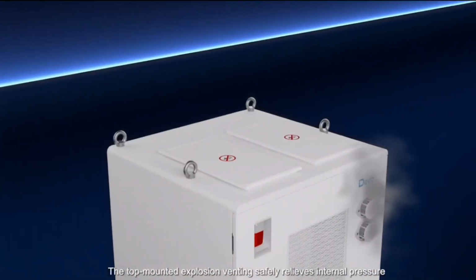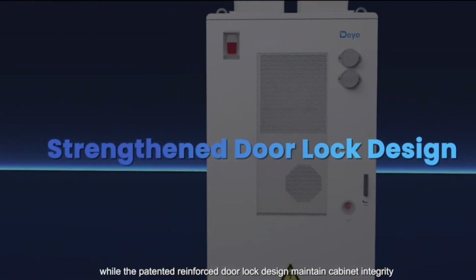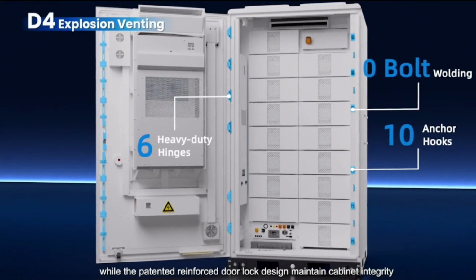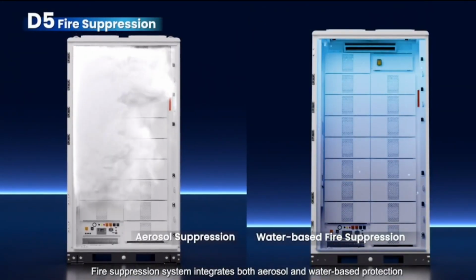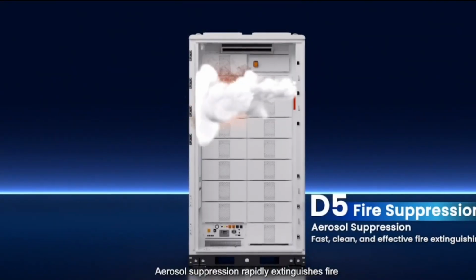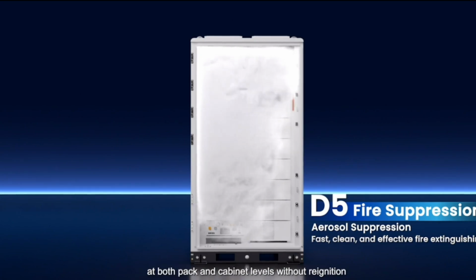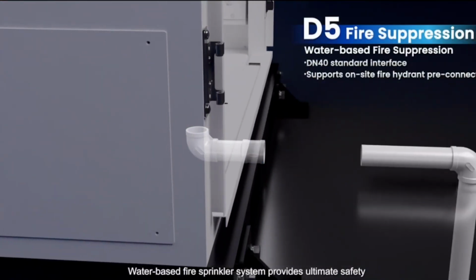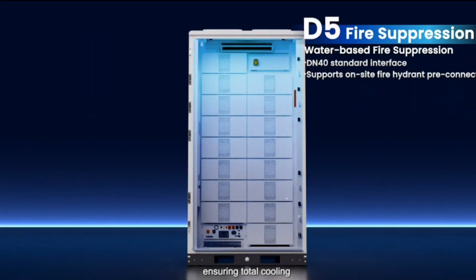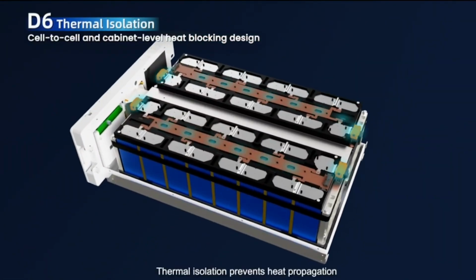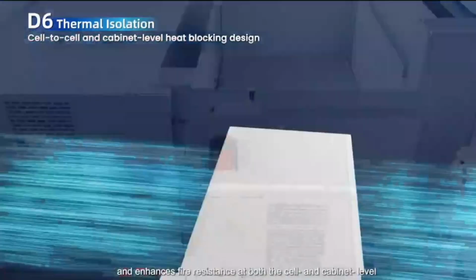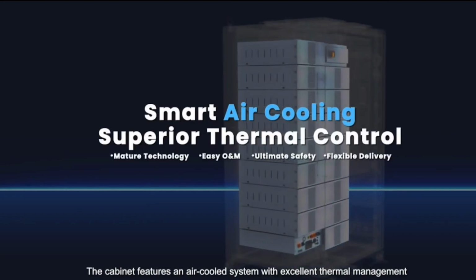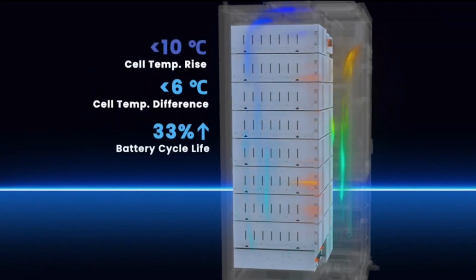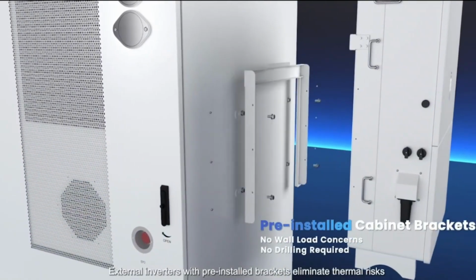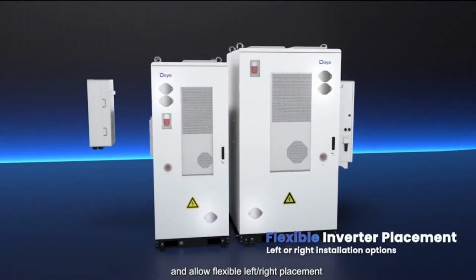The top-mounted explosion venting safely relieves internal pressure, while the patented reinforced door lock design maintains cabinet integrity, even under extreme thermal runaway conditions. Fire suppression system integrates both aerosol and water-based protection. Aerosol suppression rapidly extinguishes fire at both pack and cabinet levels without reignition. Water-based fire suppression provides ultimate safety via full cabinet immersion when needed, ensuring total cooling. Thermal isolation prevents heat propagation and enhances fire resistance at both the cell and cabinet level. The cabinet features an air-cooled system with excellent thermal management. External inverters with pre-installed brackets eliminate thermal risks and allow flexible left-right placement.